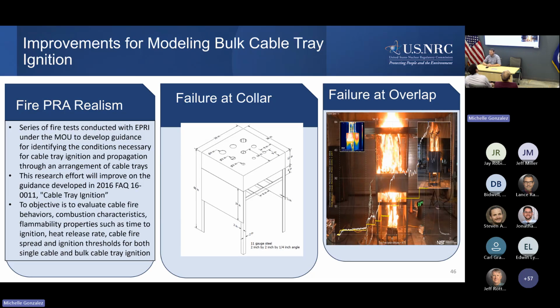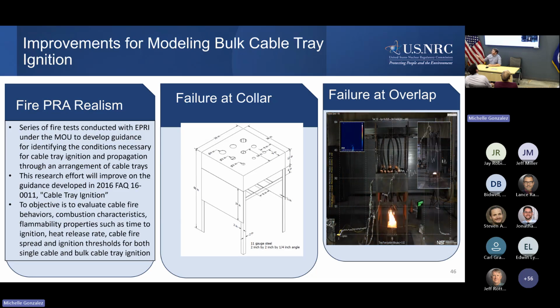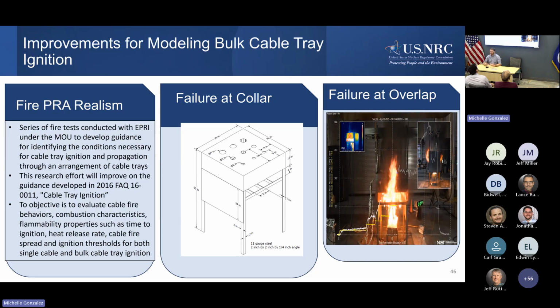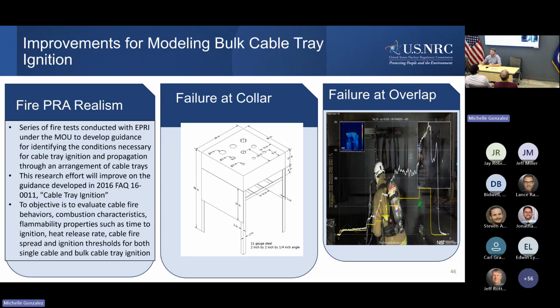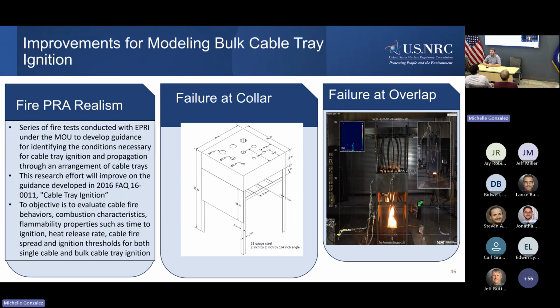This can have a significant risk impact to the plant because the cables are significant targets in terms of the fire PRA. What you're seeing in the center picture on the screen is an apparatus we developed to understand how different penetration styles on top of an electrical enclosure can influence the ability of a fire to progress from inside the enclosure and run up the cable tray or the cables themselves, potentially leading to full-scale involvement and burning of a cable tray.